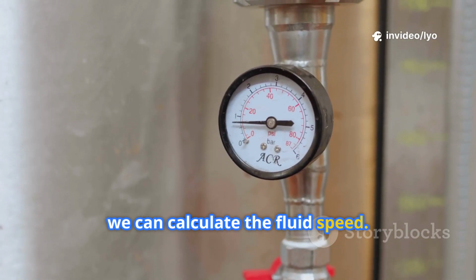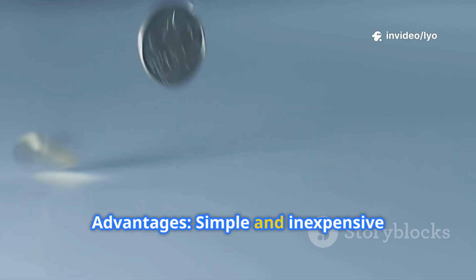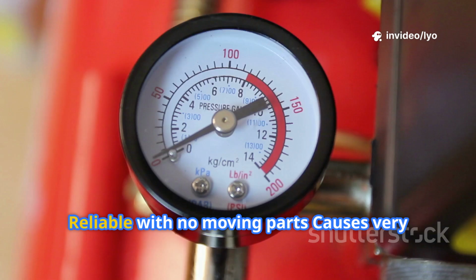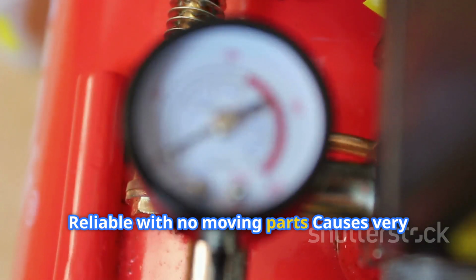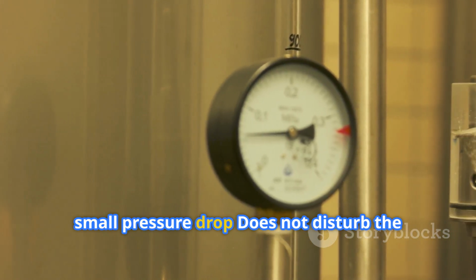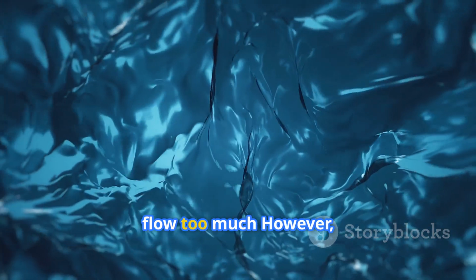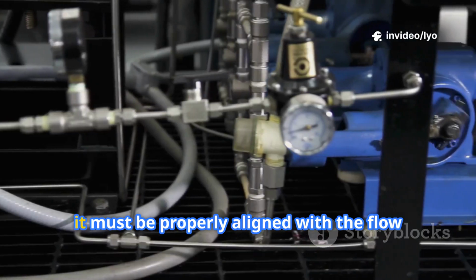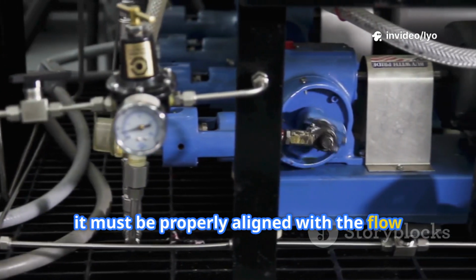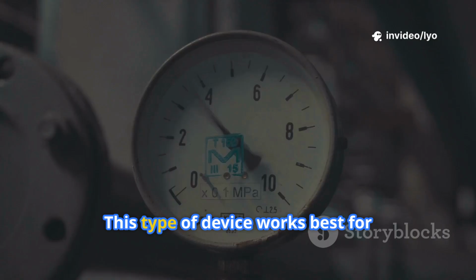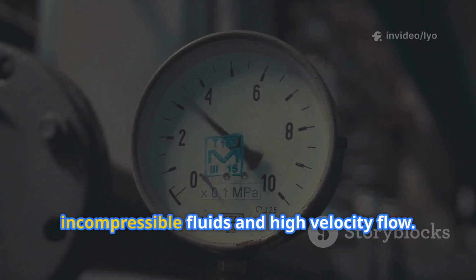fluid speed. Advantages: simple and inexpensive, reliable with no moving parts, causes very small pressure drop, and does not disturb the flow too much. However, it must be properly aligned with the flow to avoid error. This type of device works best for incompressible fluids and high-velocity flow.